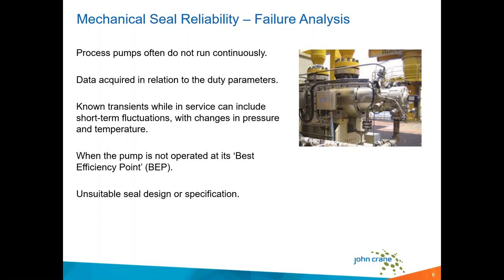And then finally, we can look at the mechanical seal and objectively say, is this the correct seal for the service? In some cases, it may not be suitable. Sometimes process conditions have changed. There may be variants introduced to the stream that weren't there before, and we have to look at material compatibility, face pressures, temperatures, and speed capability. So it's good to take an objective look at the seal, especially in a high visibility or repeat failure situation, and make sure it's still suitable for the application.